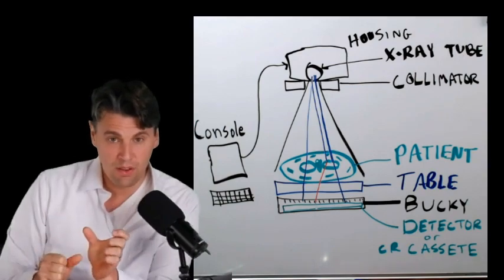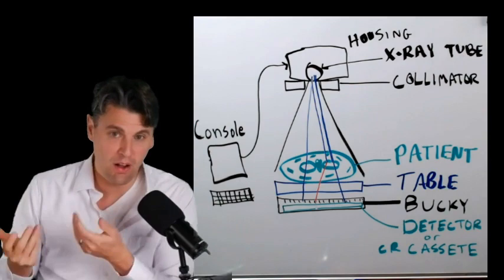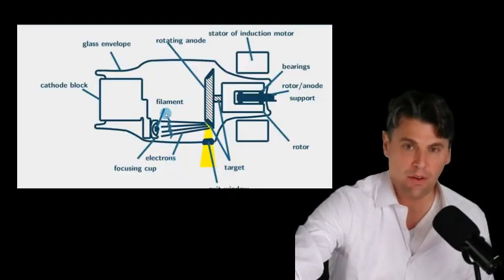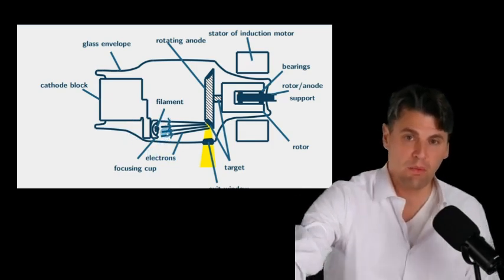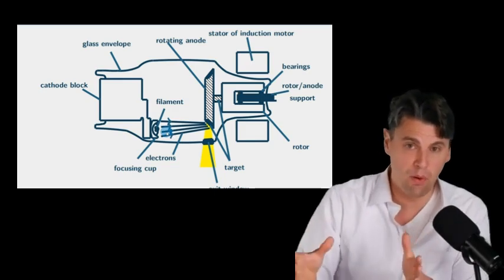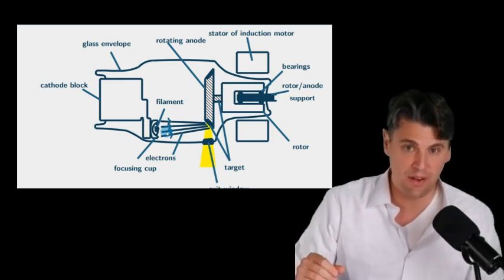In order for those electrons to get pulled over to hit that heavy metal hard, we need what we call a high voltage potential. Here's an image of that. We have what we call the cathode is where those electrons get boiled off. So there's something called a filament that we heat really hot, the electrons get boiled off, then they will get pulled over and hit an anode hard and then out come the x-rays.